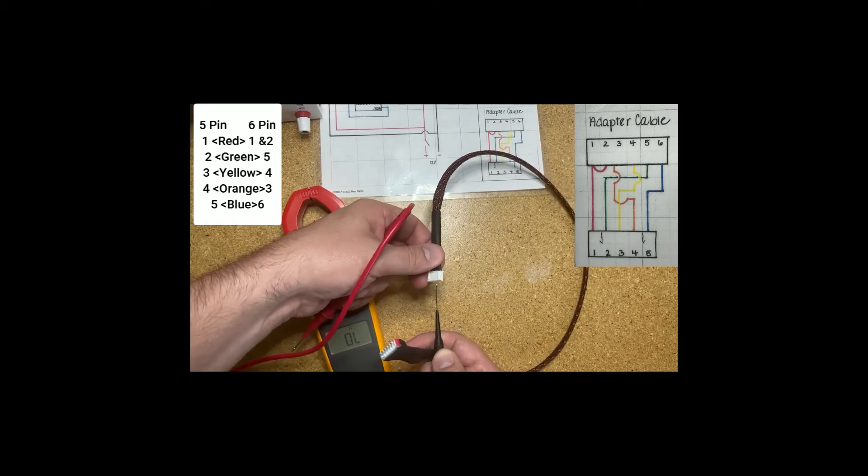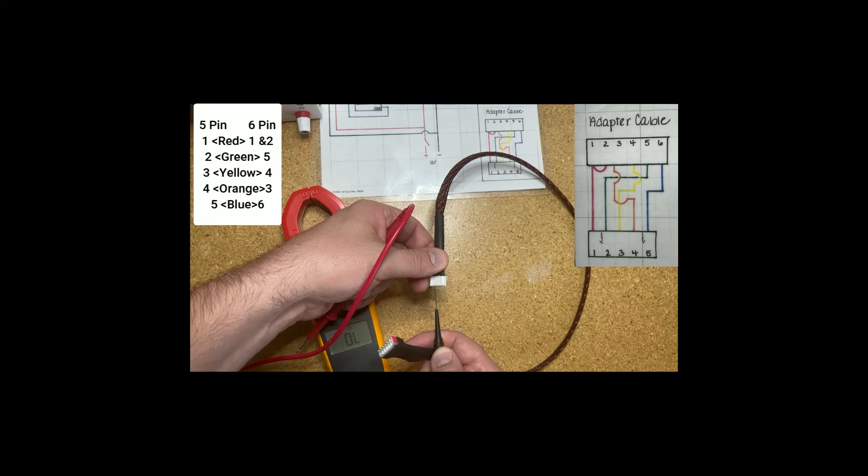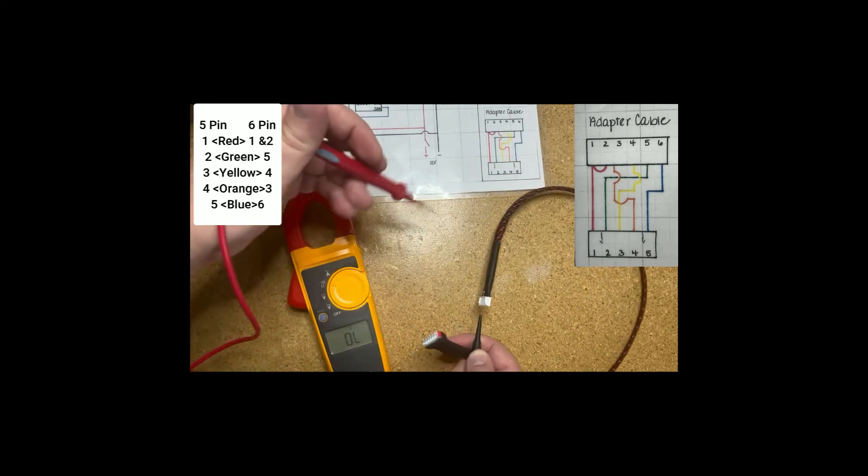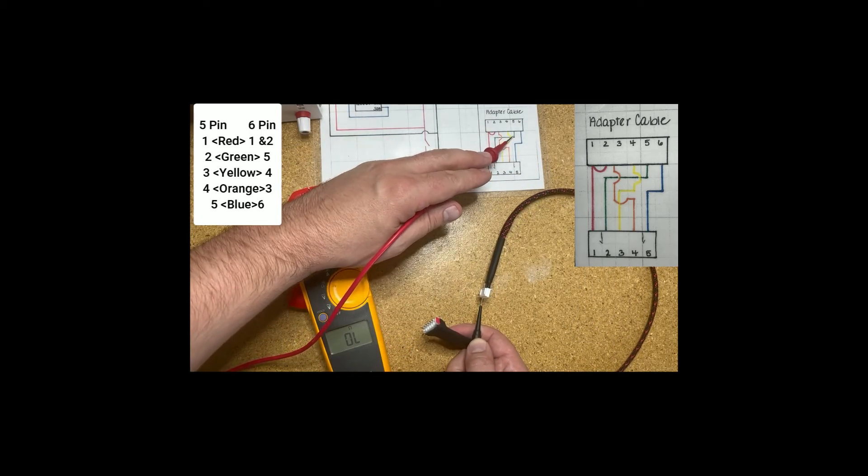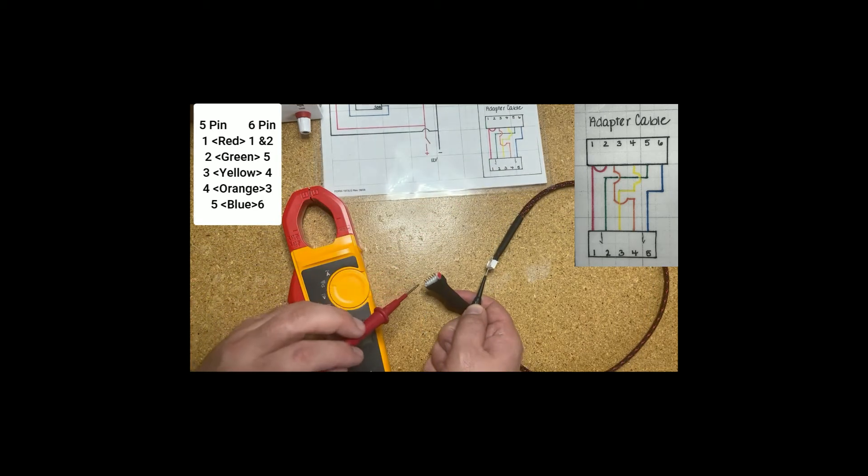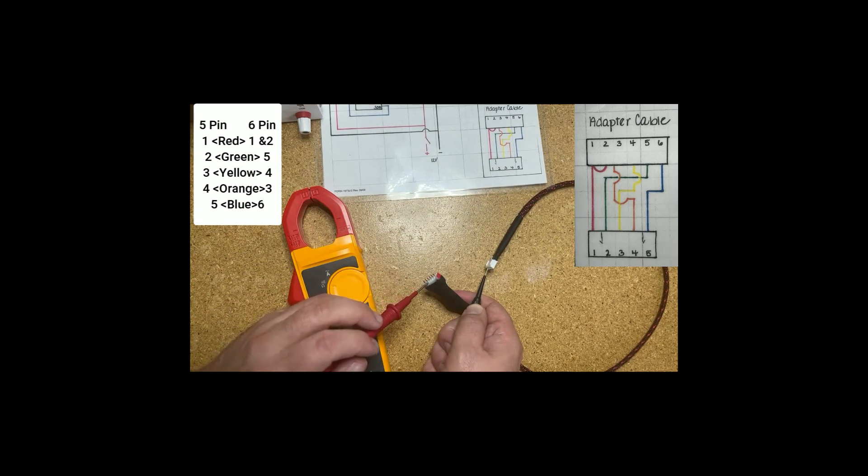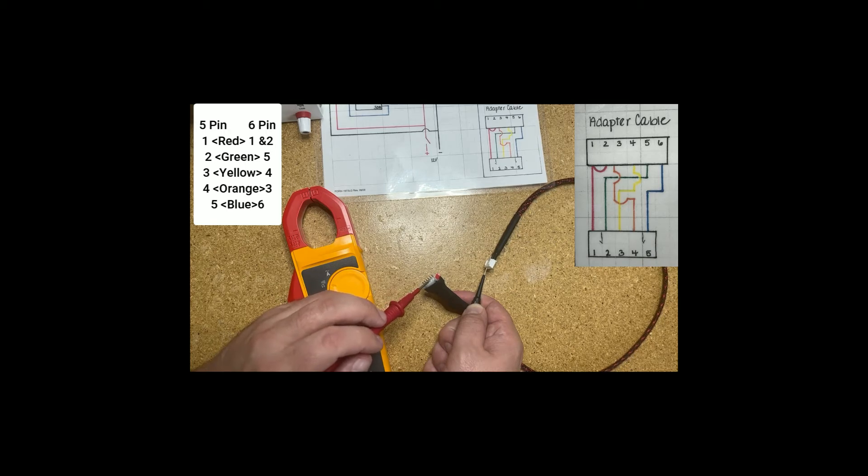Now if I bump over to the next five pin lead or five pin connector it's shown as green here. I can trace that out and that should go to pin five. So that should be this pin here. Continuity. Good. And then nothing else. Check them all to make sure there's no shorts.